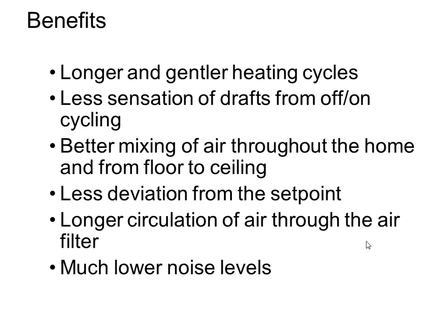The modulating gas valve is going to give you much longer heating cycles. Like I said, it's quite possible during the day, on a fairly cold day when it's 20, 30 degrees outside, your gas valve's not going to shut off at all. You get very, very long heating cycles, specifically with this type of modulating gas valve. Not all modulating gas valves do it this way, but this one does.